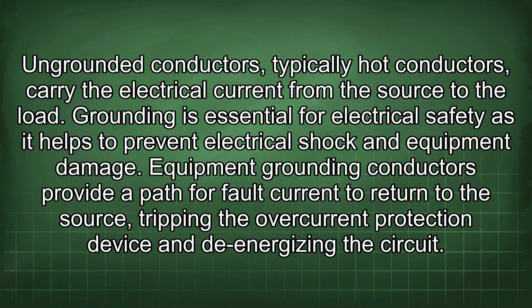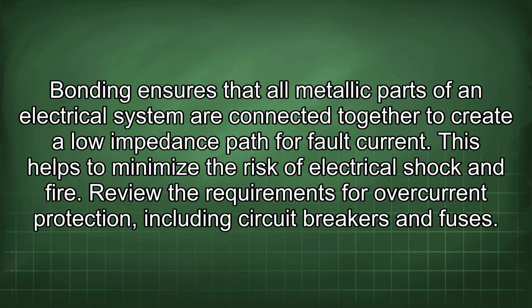Equipment grounding conductors provide a path for fault current to return to the source, tripping the overcurrent protection device and de-energizing the circuit. Bonding ensures that all metallic parts of an electrical system are connected together to create a lower impedance path for fault current. This helps to minimize the risk of electrical shock and fire.